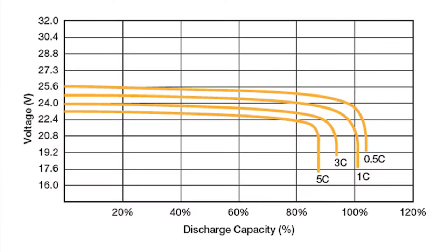Do all batteries have this effect? No. When looking at the same diagram but for a lithium battery, you can see that even at 1C the capacity is slightly higher than the rated amp-hour value. Even at a discharge of 3C — so 3 times the capacity, 300 amps in this case — the capacity is still about 90%.